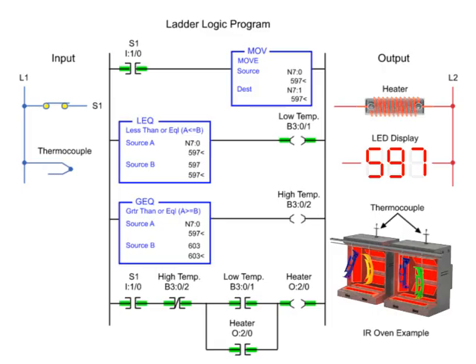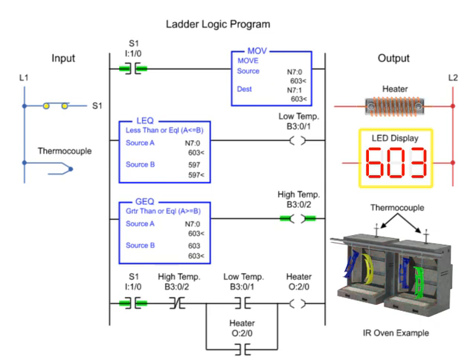In this on-off temperature control example, the heater turns on when the temperature falls to or below 597 degrees and turns off when the temperature reaches 603 degrees or more. To control the circuit, S1 is programmed in the heater output circuit.